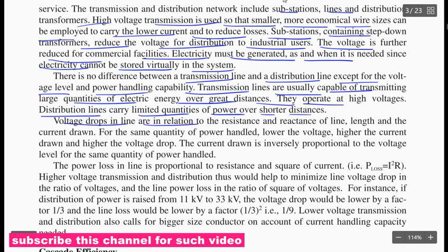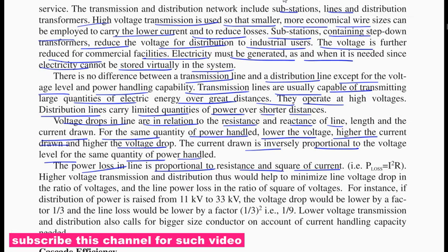Voltage drop in the line is related to the resistance and reactance of the line, the length, and the current drawn for the same quantity of power handled. Lower the voltage, higher the current drawn, and higher the voltage drop. The current drawn is inversely proportional to the voltage level for the same quantity of power handled. The power loss in the line is proportional to the resistance and the square of the current, that is, power loss equals I squared R.